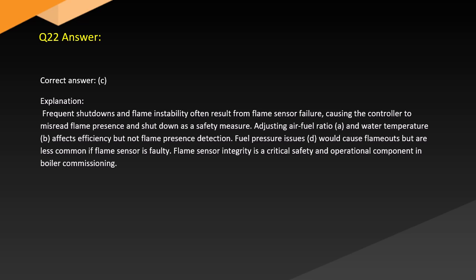Answer. Correct answer. C. Explanation. Frequent shutdowns and flame instability often result from flame sensor failure, causing the controller to misread flame presence and shut down as a safety measure. Adjusting air-fuel ratio, A, and water temperature, B, affects efficiency but not flame presence detection. Fuel pressure issues, D, would cause flameouts but are less common if the flame sensor is faulty. Flame sensor integrity is a critical safety and operational component in boiler commissioning.